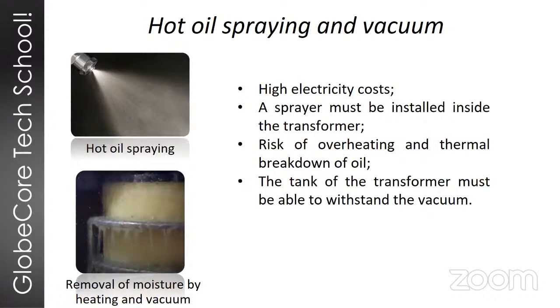Okay. Some of the other limitations here is the relatively low efficiency because, again, we have heat losses through the walls of the transformer tank. And it's also possible to overheat the oil inside the heater. And as we know, the high temperature breaks the oil molecules. The problem here is that usually you have the oil processing machine connected to the transformer by hoses, and to get the necessary temperature in the transformer, due to heat losses in the hoses, the temperature of the oil in the heater should be around 140 degrees Celsius, and that is not very good for the oil. You can damage the oil doing that.